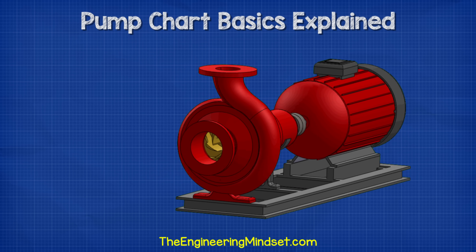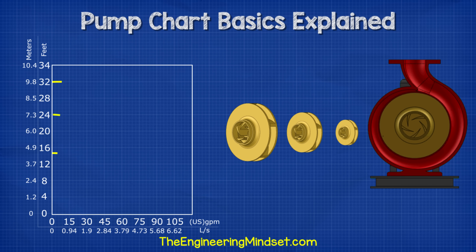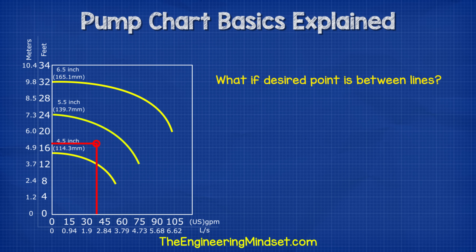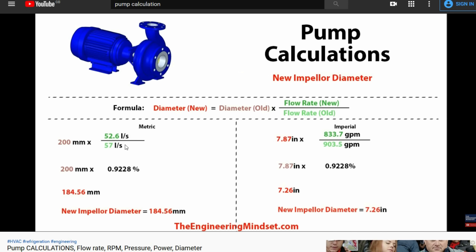Impeller size. With centrifugal pumps, we can often change the size of the impeller. The diameter of the impeller will change how much water can be moved. So on some charts, you'll see multiple performance curves which will give us the performance details of the pump for different diameter impellers. For example, 30 gallons per minute for a 4.5 inch impeller gives us around 13 feet of head, but if we use the 5.5 inch impeller, then we would get around 22.5 feet of head. In some instances, our required flow rate and head pressure might fall between the two impeller diameter lines — in such cases, we can often machine the impeller down to the required size to get a better match. You should ask your pump manufacturer or pump specialist to carry out this service, and the performance of the pump will then need to be calculated.